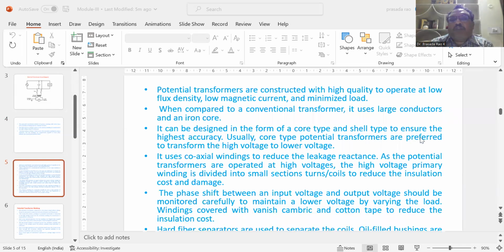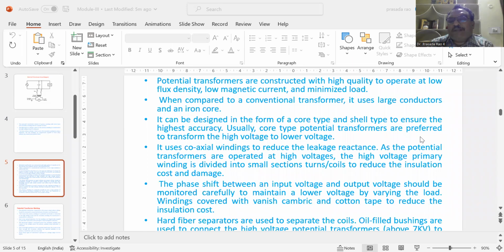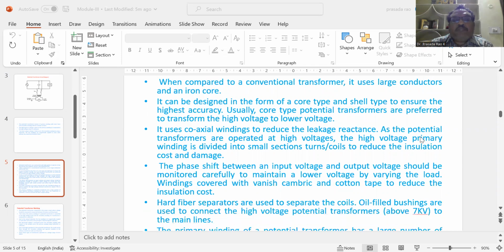It can be designed in the form of a core type and shell type to ensure the highest accuracy. Usually, core type potential transformers are preferred to transform the high voltages to a lower voltage. It uses a coaxial winding to reduce the leakage reactances. As the potential transformers are operated at high voltages, the high voltage primary winding is divided into small sections to reduce the insulation cost and damages.